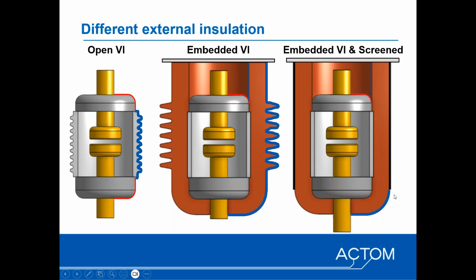But now you may say that this distance may be shorter than what you would normally have with normal embedded epoxy. But in terms of screened switchgear, all the connections to the high voltage components like bus bars and cable connections are done through screened separable connectors, which basically form an earth layer on the outside exposed to the atmosphere, where the inside surface is sealed off from the atmosphere, and it is controlled by the interface fit between the screened separable connector and the actual switchgear module.